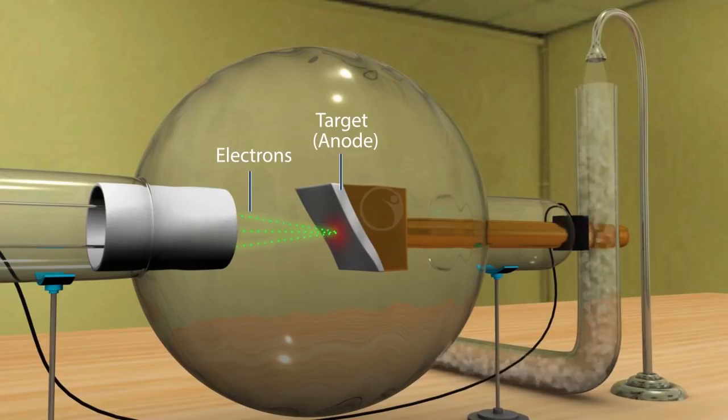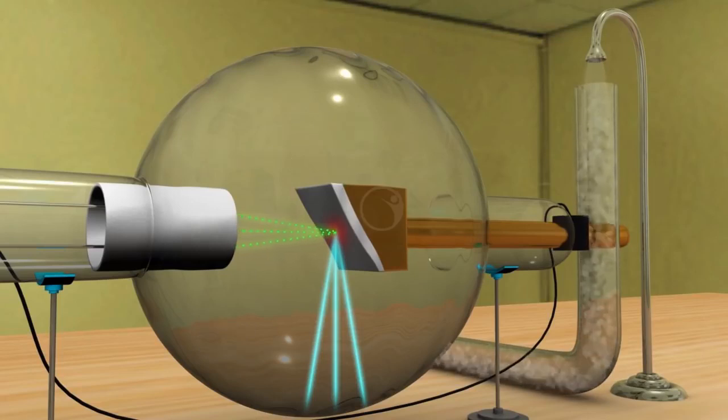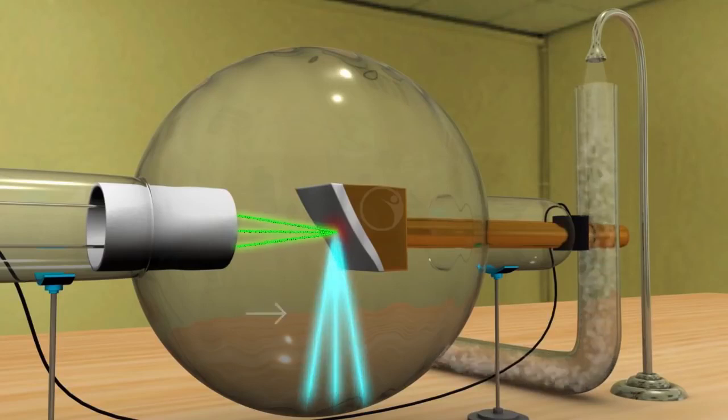When it hits, the kinetic energy is transferred to produce x-rays. The intensity of the x-rays depends on the number of electrons striking the metal target. So, if we can increase the rate of electrons emitted by the filament by increasing the current flowing through the filament, then we can increase the intensity of the x-rays.